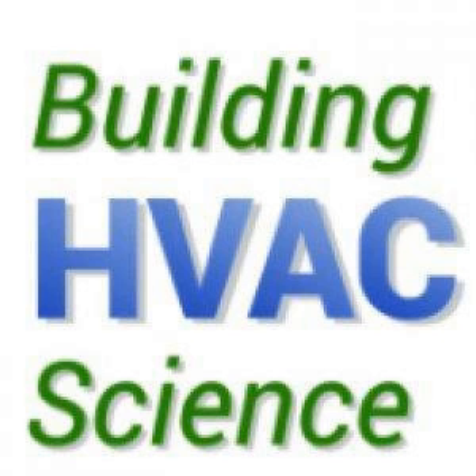There's a big difference in how you treat the data depending on the time of year. If it's the hottest day of the year and you're taking inbound traffic like crazy, you're not going to go to that system with a 9-degree split where the homeowner's comfortable and make sure they take care of it now. But if it's March, not yet the hottest time of year, and that system's operating with a 9-degree split when it's 85 degrees outside in Texas, well then you know that's going to be a call at some point.